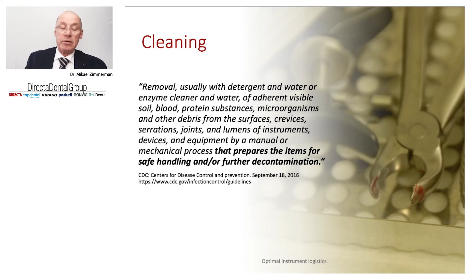That should prepare the items for further safe handling and decontamination. Ultrasonic baths are extremely effective methods of cleaning your instruments, and the ultrasonic bath is actually about 100 times more effective in removing blood contamination than manual cleaning. And the maximum effect of a good ultrasonic bath is usually after 5 to 10 minutes processing time.